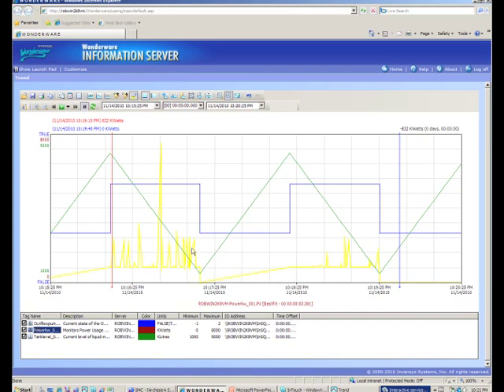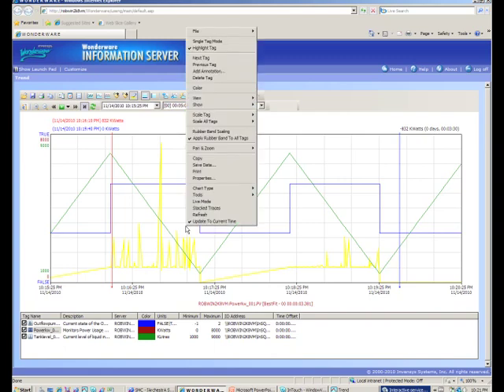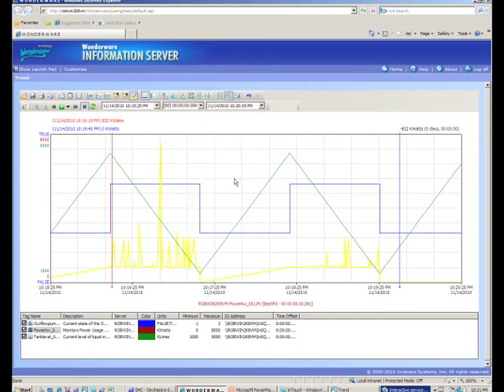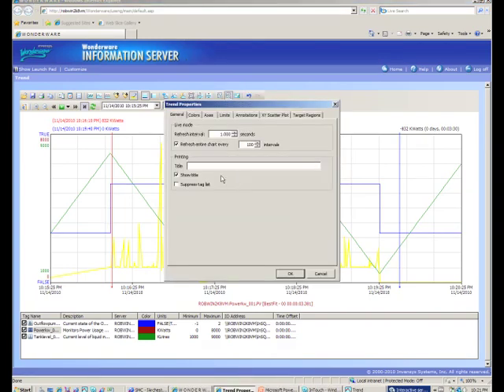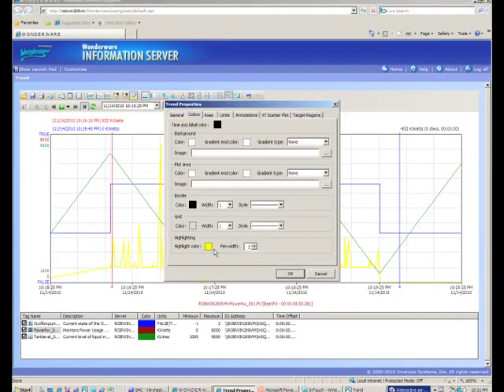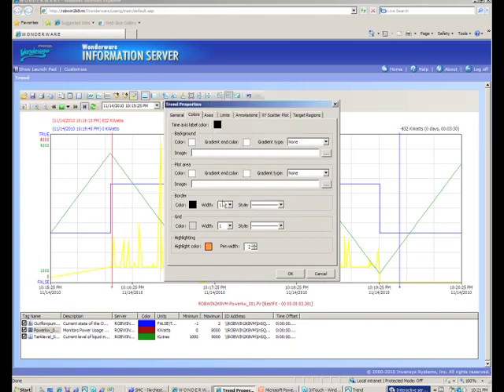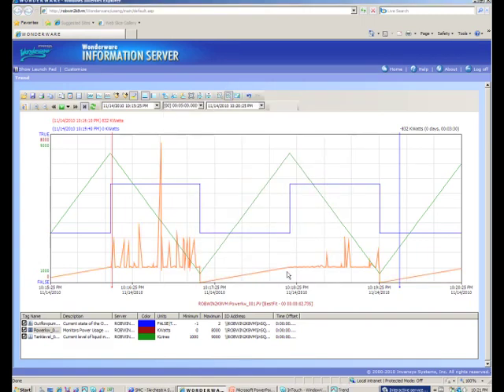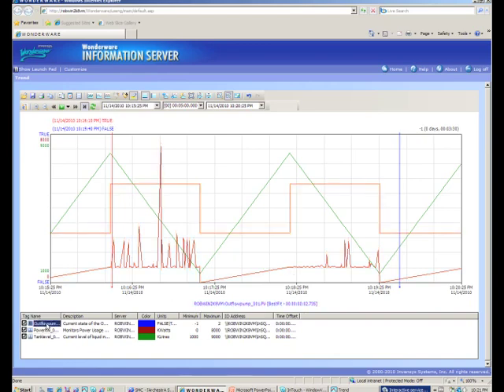I find this a little hard on the eyes for most users so what I'm going to do is I'm going to go to properties and I'm going to change the property of the highlight and change the color to something a little less glaring. After I've done that we'll note that now if I click on the outflow pump we can see everything in relation to the outflow pump. For example the tank level starts to drop when the outflow pump comes on, power usually begins to go up.